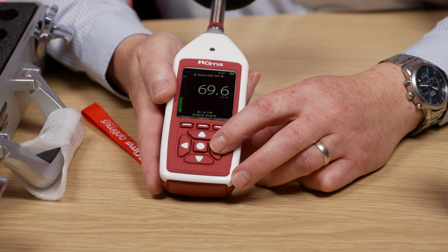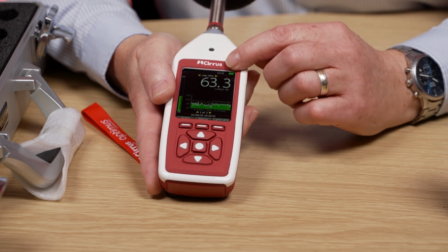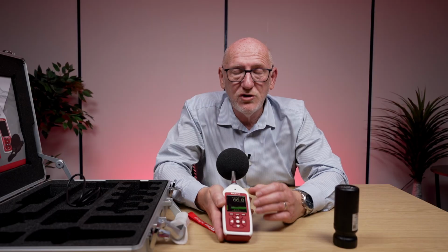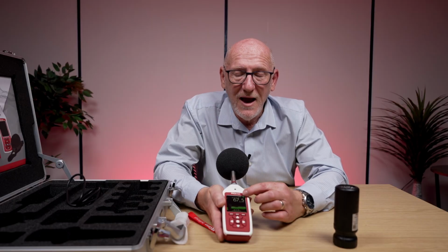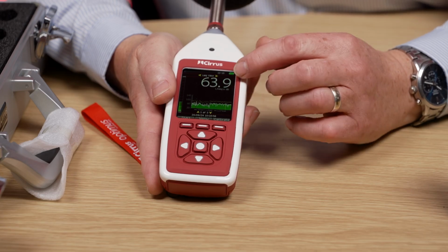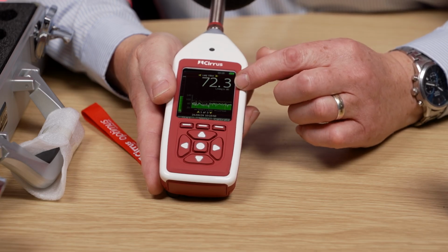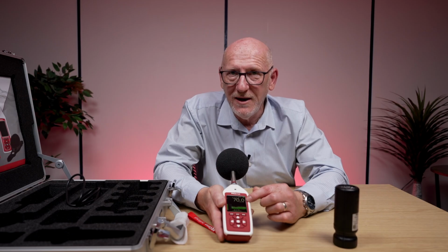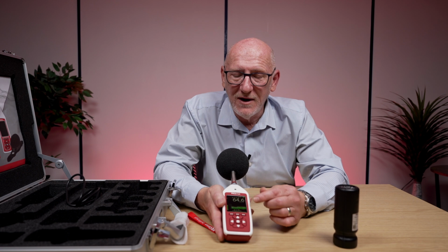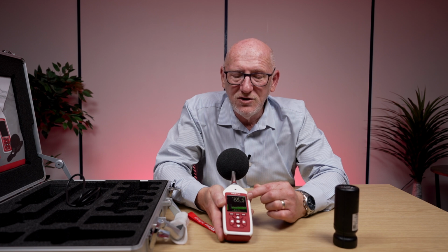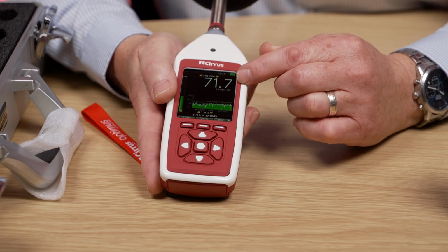I'm pressing the right hand arrow and it's taking me to the LEQ view. Remember, I'm not measuring at the moment, it's just showing you what's going on. LEQ is basically a logarithmic average of the noise levels, and that large number at the top has got some slightly different lettering underneath. LAEQ 1S dB: a decibel level, sound level of course, A-weighted, and it's the 1 second logarithmic average of the noise level. So it's not changing quite as fast as the previous screen.